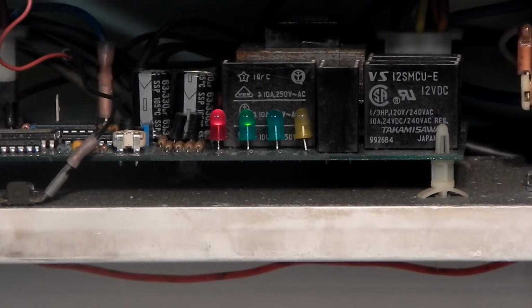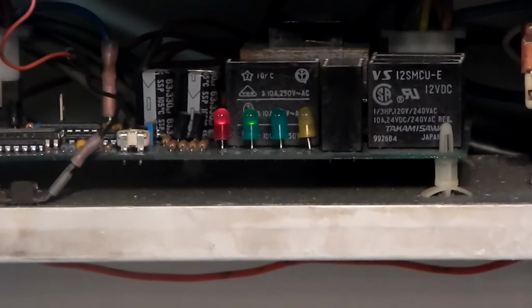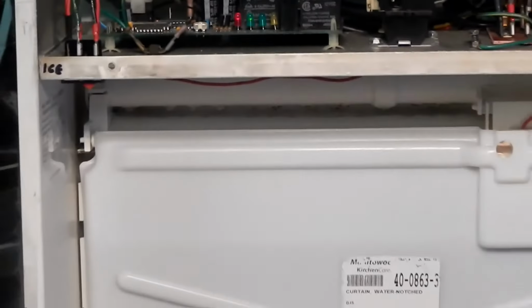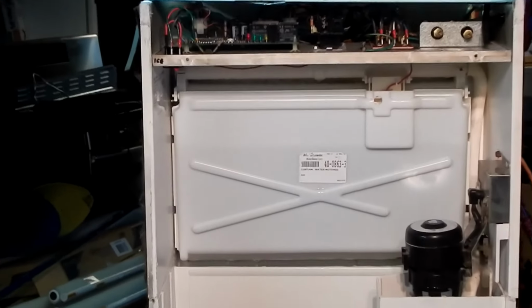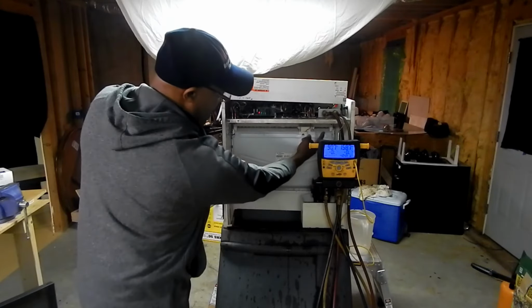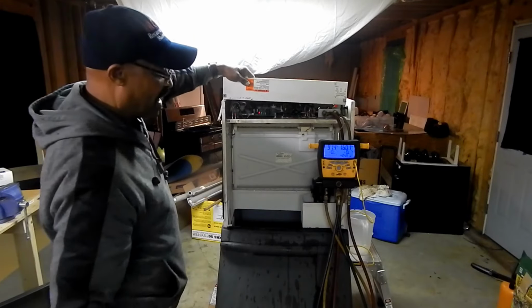For another cycle. Now it appears that the light is staying on. Up, went out again. It's blinking. It's going solid again. So let's try counting now. 1001, 1002, 1003, 1004, 1005, 1006, 1007, 1008. So it looked like it took about 7 seconds after the light stopped blinking, so that means that the ice is ready. So we're going to see right now. Valve in there is going to switch. Allow hot gas to come across this plate, and the plate's going to drop the ice.